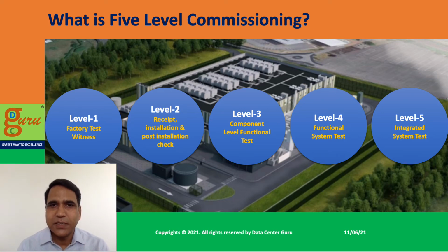Level 3 is component-level functional test. Like a UPS, just as an example -- the UPS has a box in itself, and then a battery, and there are certain cables connecting the UPS to the battery, and then input and output supply, right? So you have to check all the elements of the UPS. You have to check whether the cables are adequately sized, and whether insulation levels and amperage capacities are enough.